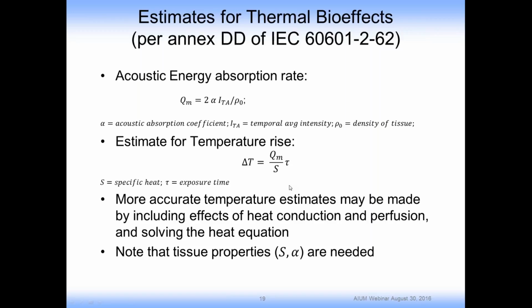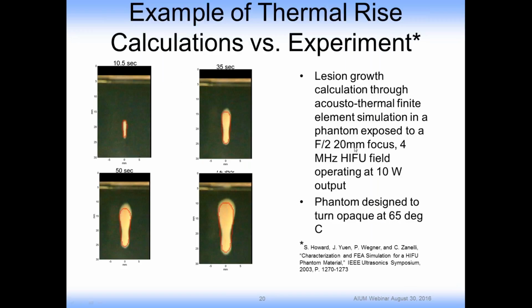Now, as I mentioned, more accurate temperature estimates may be made with thermal modeling. In all cases, however, the specific heat and acoustic absorption properties, as well as the density, are needed for the tissue model that you have in mind. I'm going to show, for purposes of illustration, the type of data that you could try to get from this. This is for a phantom and some measurements that we did a while back.